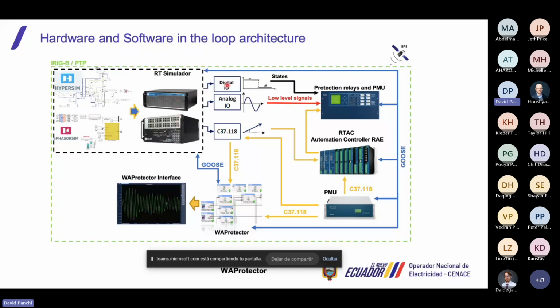We transfer the data, the logical data or the analog data, to the PMUs by low-level signals or the virtual PMUs. And these signals are transferred to the PMU relays, and the PMU relays transfer the phasor measurements to the WAMS system. The WAMS system processes the data and applies some logics of protection or control. If a condition is satisfied, we send the trip to the simulation by a GOOSE message. So with this architecture, we can test control and protection schemes that we will implement in the real power system.